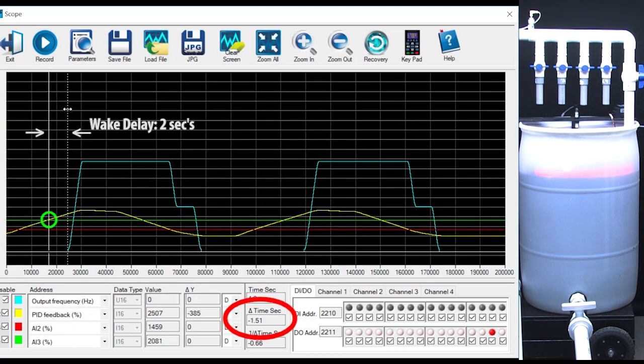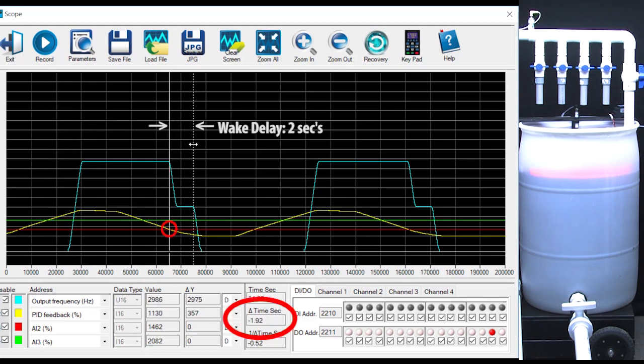we see the drive woke up the motor 2 seconds after the process variable crossed the green wake up threshold and it shut the motor down 2 seconds after crossing the red sleep threshold.